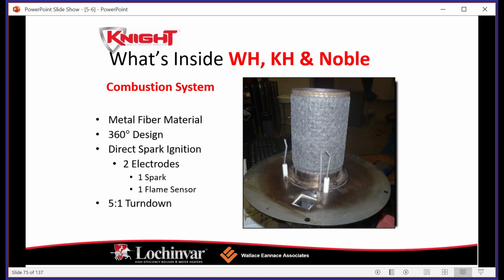The thing about NOx is it isn't necessarily an ozone depletion air quality issue, it's a smog issue, okay? So we're not necessarily worried about the potential impact of the flue gases on our air quality for ozone depletion. I mean, that's the carbon molecule, it's a whole different ball of wax. But what we are doing with our NOx compliance is staying within our regulatory requirements for smog. So again, California, Utah, Texas, if I recall correctly, have very stringent NOx requirements. In less populated areas, you're not going to see it as much.